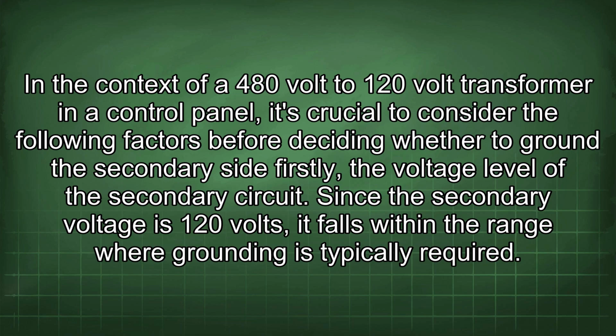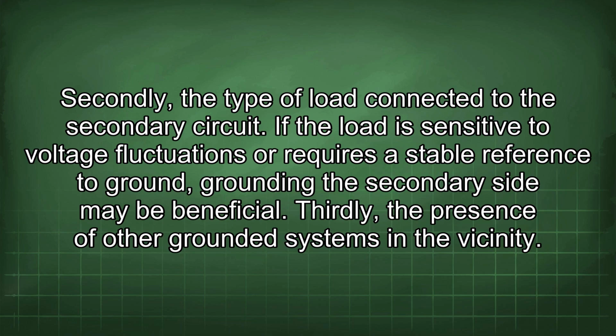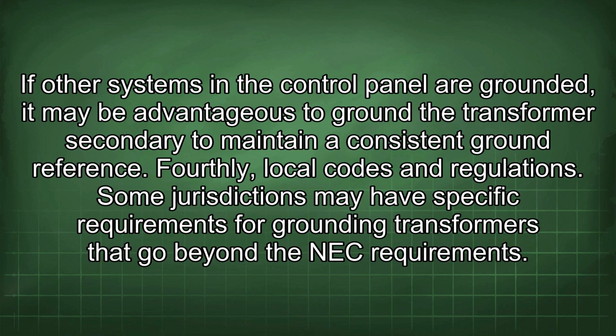In the context of a 480-volt to 120-volt transformer in a control panel, it's crucial to consider the following factors before deciding whether to ground the secondary side. Firstly, the voltage level of the secondary circuit. Since the secondary voltage is 120 volts, it falls within the range where grounding is typically required. Secondly, the type of load connected to the secondary circuit. If the load is sensitive to voltage fluctuations or requires a stable reference to ground, grounding the secondary side may be beneficial. Thirdly, the presence of other grounded systems in the vicinity. If other systems in the control panel are grounded, it may be advantageous to ground the transformer secondary to maintain a consistent ground reference. Fourthly, local codes and regulations. Some jurisdictions may have specific requirements for grounding transformers that go beyond the NEC requirements.